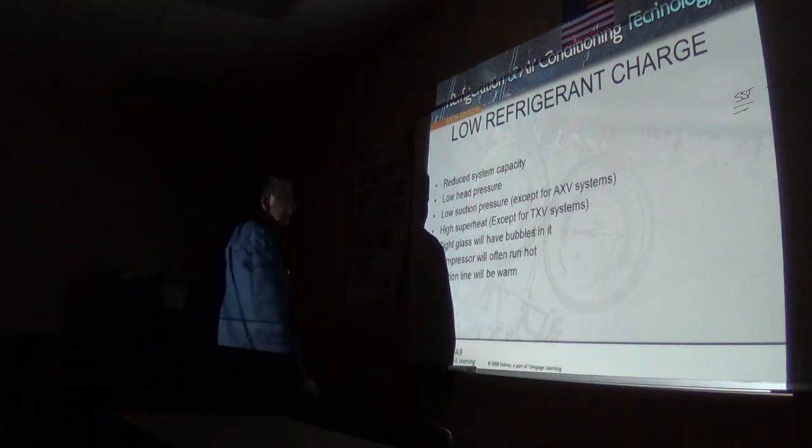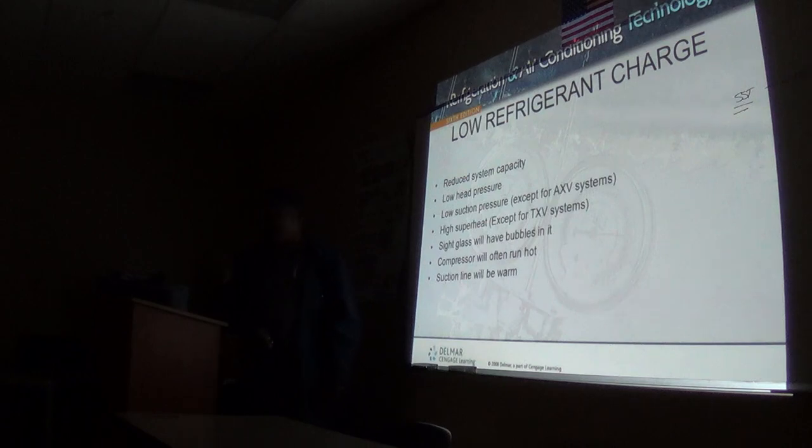So you think to recover it all, leak test it, or just put the gas in? Shut down the system, and if you have some nitrogen, pressurize with nitrogen and look for a leak with soap liquid. But I would definitely advise, if your leak is to that point, you need to evacuate it anyway. Evacuate it, then leak test.